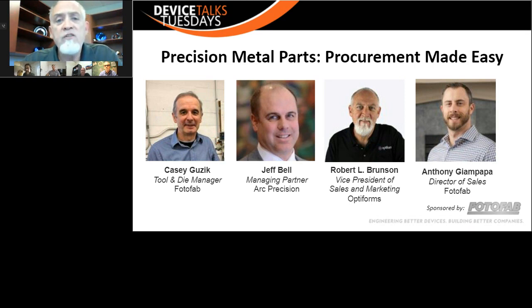We start off with a piece of stainless steel, a 17-4 stainless steel mandrel that's usually a convex shape that we optically polish and hard chrome. We then put that into our electroforming tanks and we plate anywhere from maybe a half to 1 millimeter thick on average of a substrate. Once the desired thickness is built up, we remove that component and we now have a freestanding optical shape, whether it's an ellipse or a parabolic or a condenser, whatever it might be.